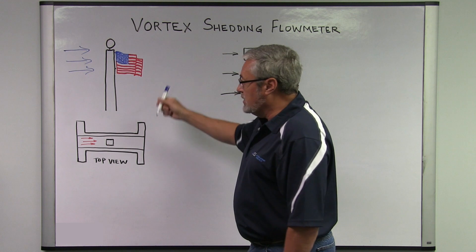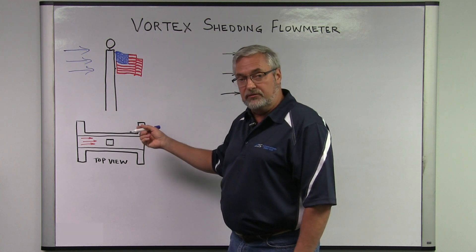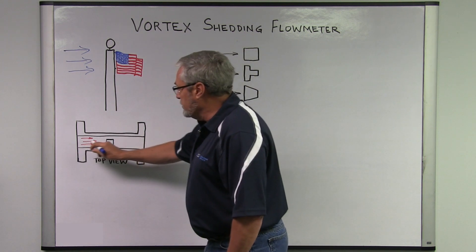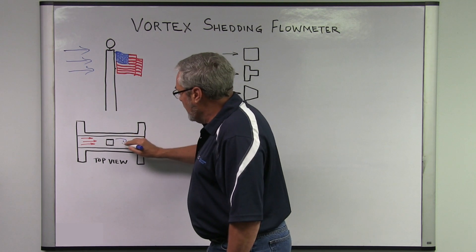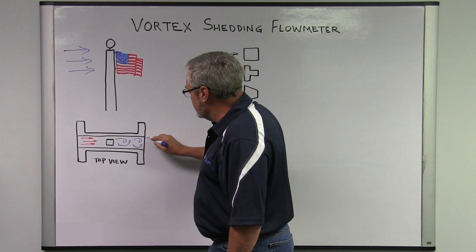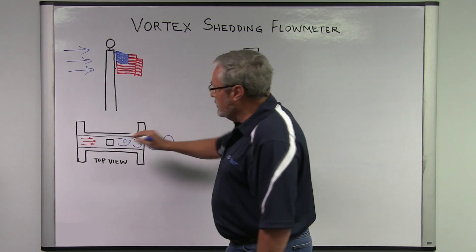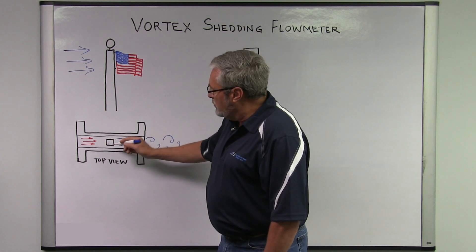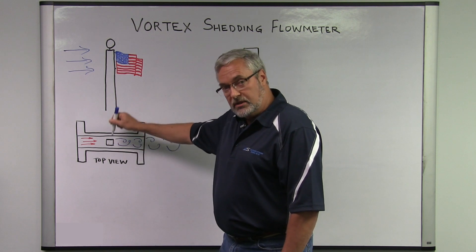The same thing can be used in today's vortex meters by generating a turbulent flow in a vortex street. With fluid flowing around the bluff body, you get alternating high and low pressure zones downstream, which can be measured by the deflection of a shedder bar.